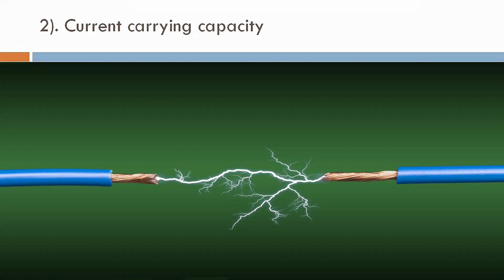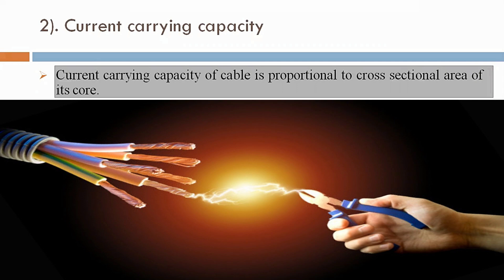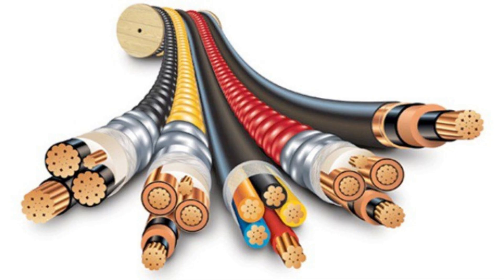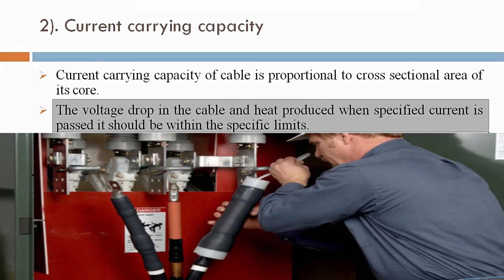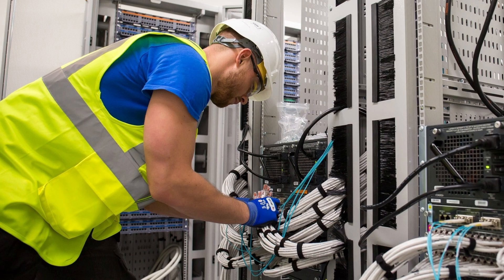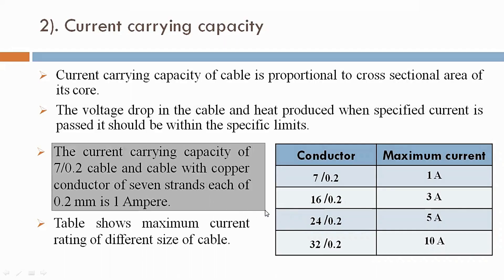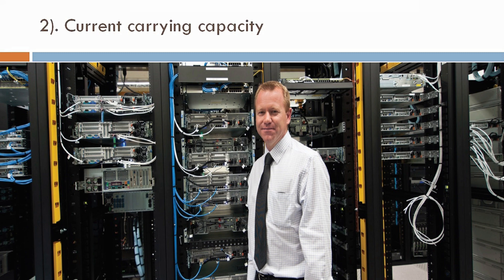Now second point: current carrying capacity. Current carrying capacity of cable is proportional to the cross-sectional area of its conductor. The voltage drop in the cable and heat produced when specified current is passed should be within the specific limit. The current carrying capacity of 7/0.2 cable — a cable with copper conductor pair of 7 strands each of 0.2 mm — is 1 ampere.